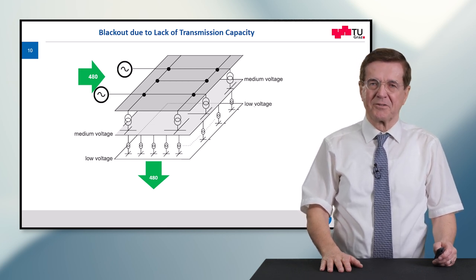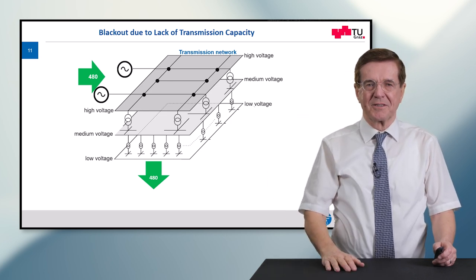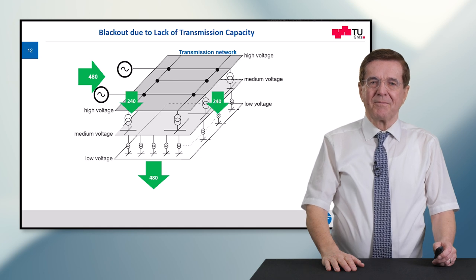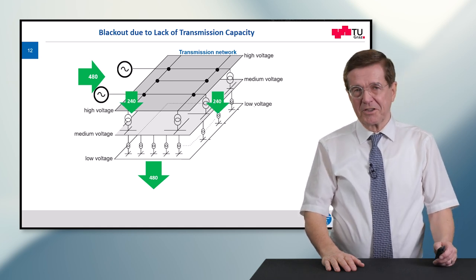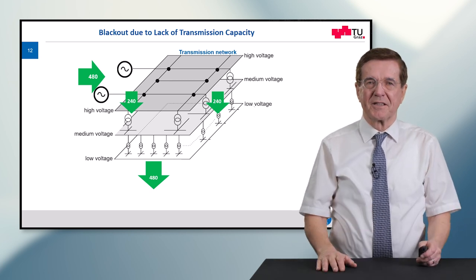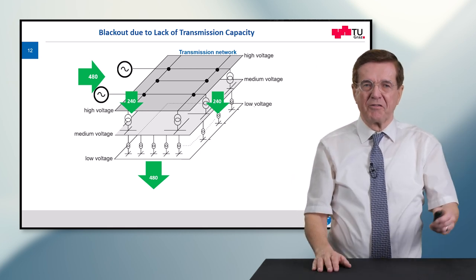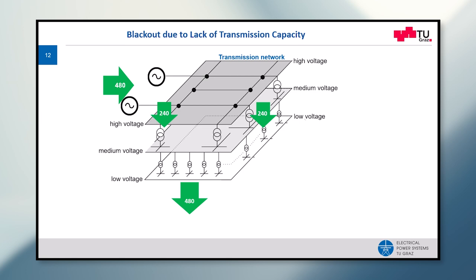The transmission grid through medium voltage provides the energy from the high voltage level down to the consumers. Now the transmission network is split into two parts — a left part and a right part — and each side can supply 50 percent of the full power. From left to right we must transport 240 megawatts, carried out in three parallel lines which share their burden, so 80 megawatts for each of them.